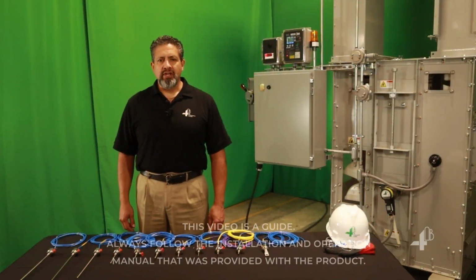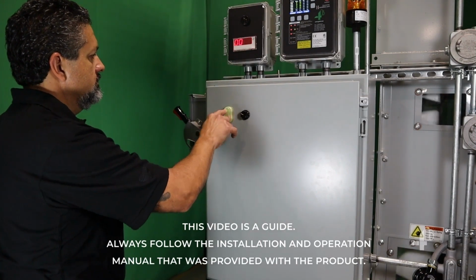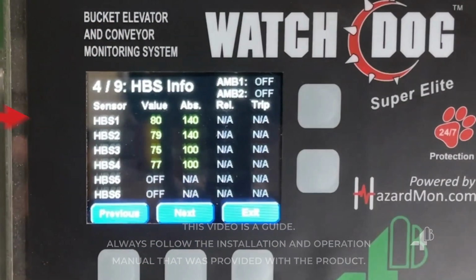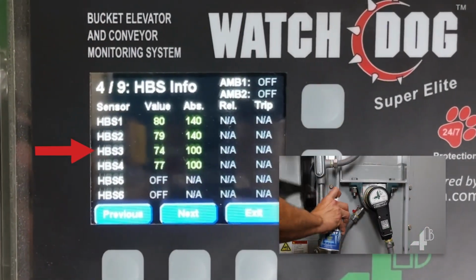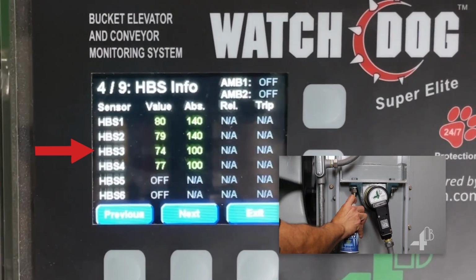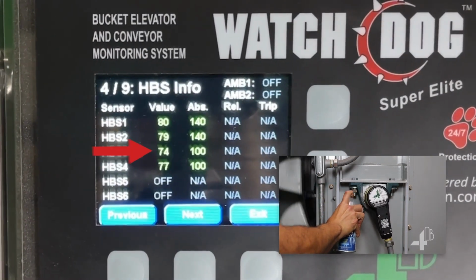Do not introduce product during commissioning and testing. Start the machine and observe the temperature on the screen. Apply a thin coat of cold spray onto and around the sensor housing, then observe that the temperature is reduced.